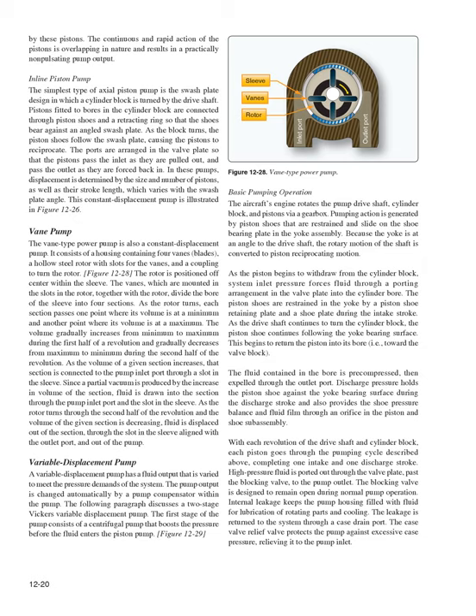As the volume of a given section increases, that section is connected to the pump inlet port through a slot in the sleeve. Since a partial vacuum is produced by the increase in volume of the section, fluid is drawn into the section through the pump inlet port and the slot in the sleeve. As the rotor turns through the second half of the revolution and the volume of the given section is decreasing, fluid is displaced out of the section, through the slot in the sleeve aligned with the outlet port, and out of the pump. Variable displacement pump.